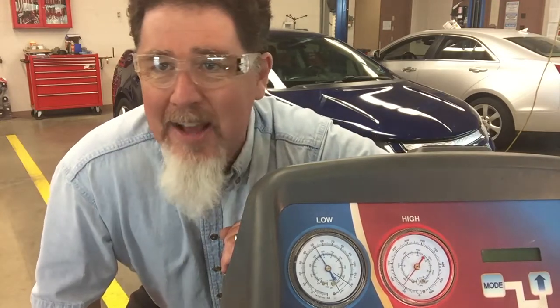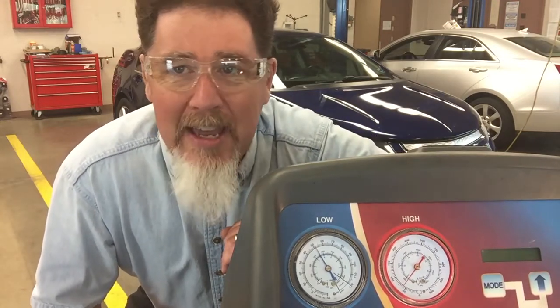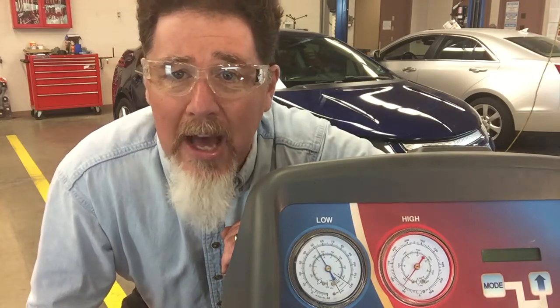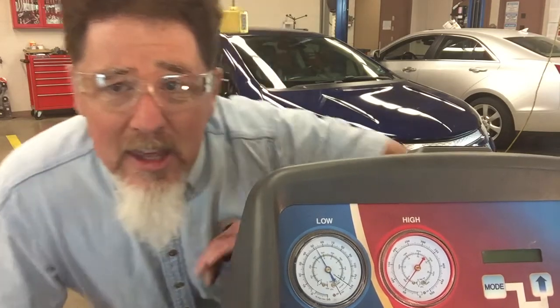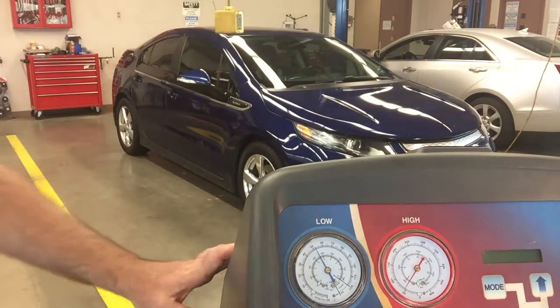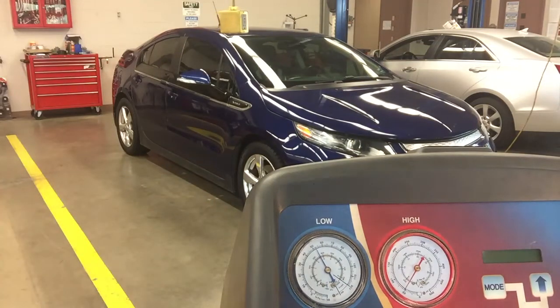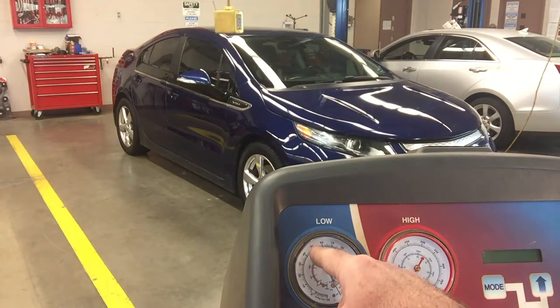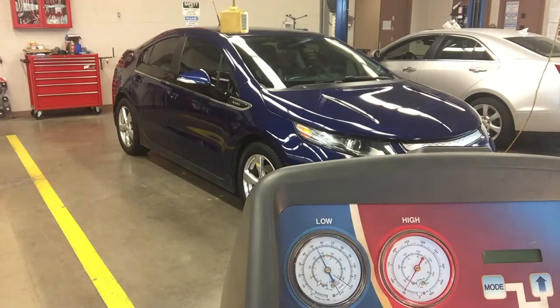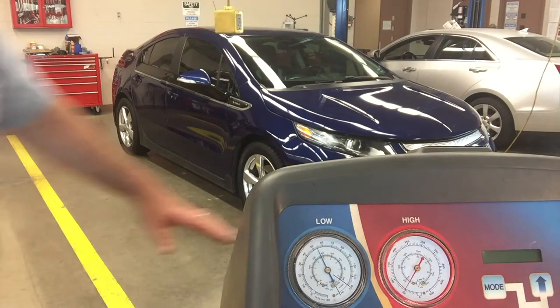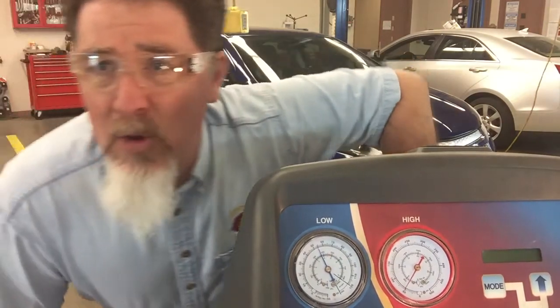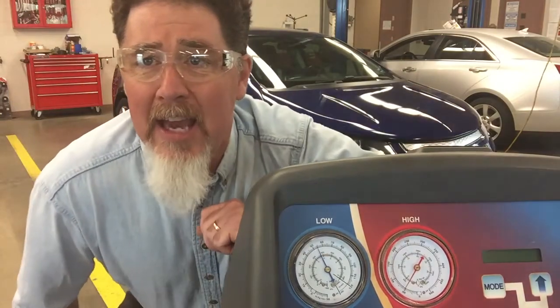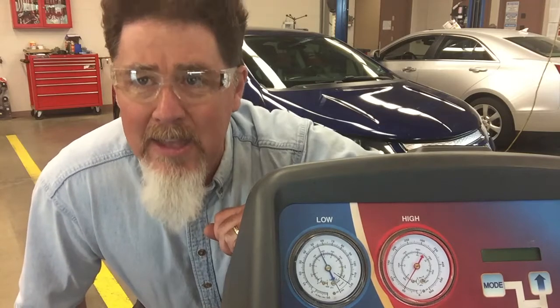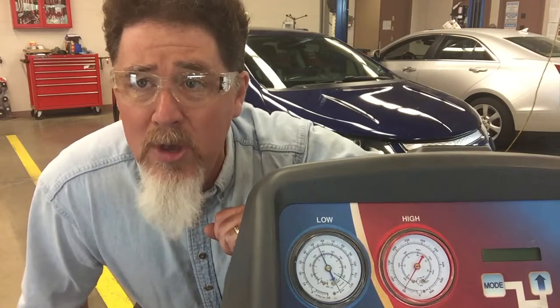And sometimes it takes only 30 seconds, maybe a minute at the most to equalize. And I'm looking at these pressures right now. I'm going to turn around and see what they're at right now. But already they equalized to around 52, 52. So that was less than 1 minute. And we could go back and watch the videos, and we can see exactly what the equalization time is. But on an orifice tube system, I would expect it to equalize that fast. This is a normal system.